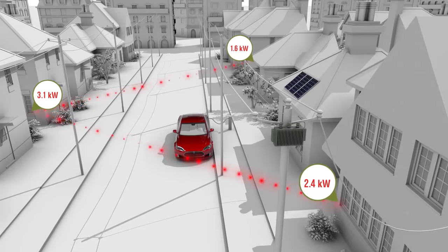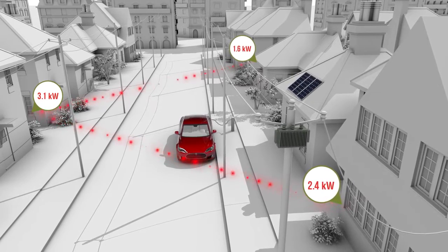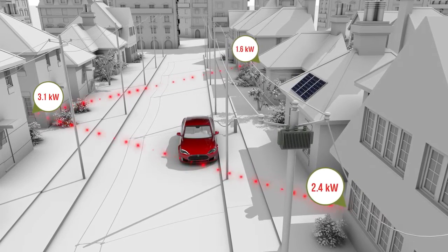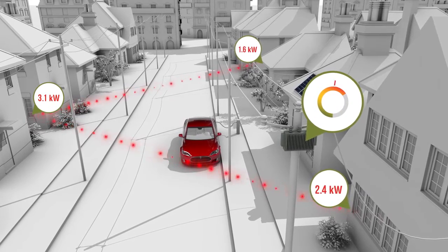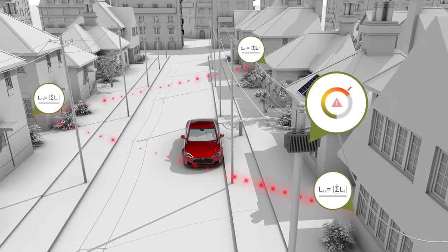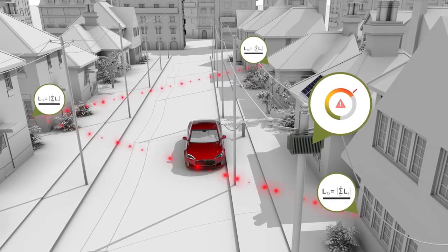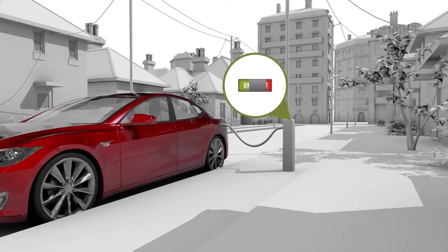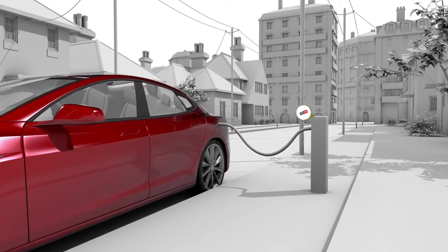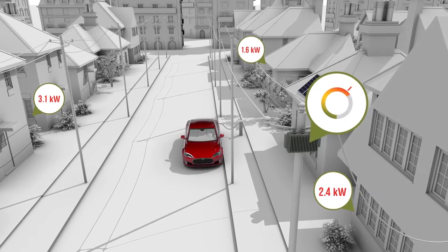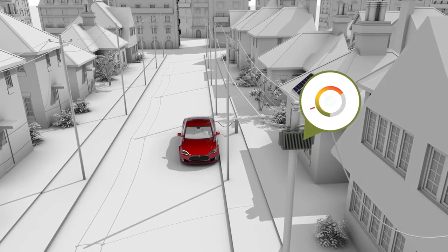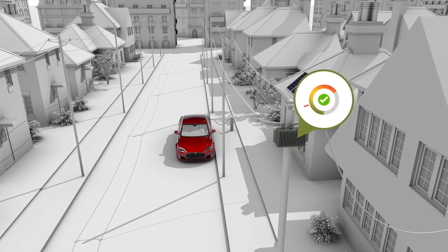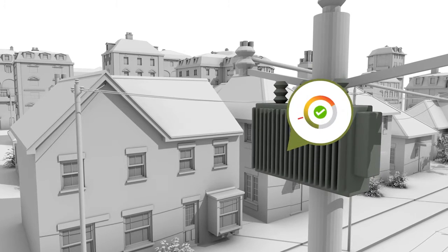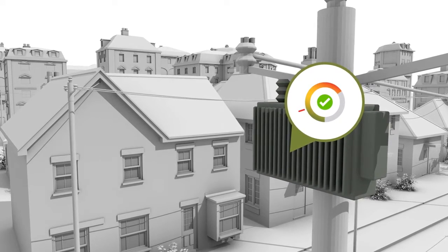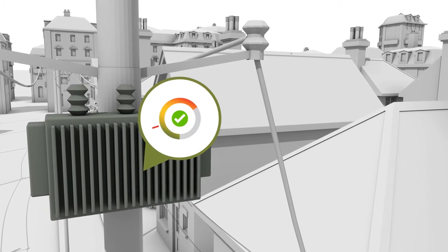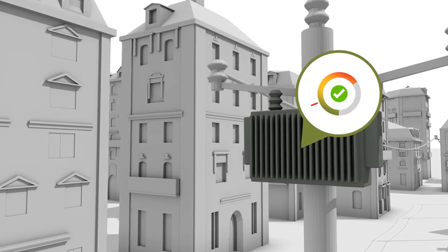Meters then communicate with each other locally to calculate the load on individual transformers and quickly identify when a transformer is approaching overload conditions. When this occurs, a distributed analytic running on the OpenWay Riva meter determines whether to shut off controlled loads behind the transformer, increase local distributed generation behind the transformer, or take other action to protect the transformer against overload and failure. Only OpenWay Riva enables intelligent devices to work together to ensure safe load levels on distribution transformers are maintained continually and service disruptions are minimized.